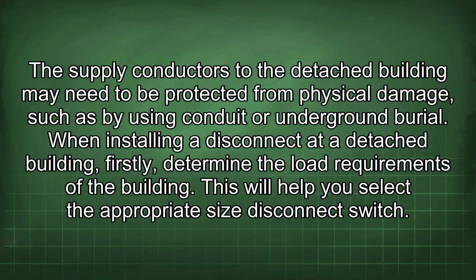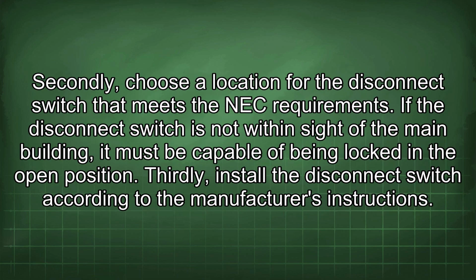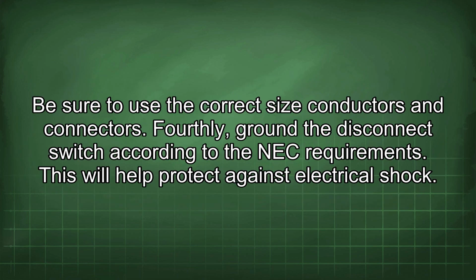or underground burial. When installing a disconnect at a detached building, firstly, determine the load requirements of the building. This will help you select the appropriate size disconnect switch. Secondly, choose a location for the disconnect switch that meets the NEC requirements. If the disconnect switch is not within sight of the main building, it must be capable of being locked in the open position. Thirdly, install the disconnect switch according to the manufacturer's instructions. Be sure to use the correct size conductors and connectors.